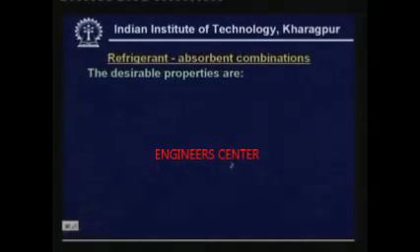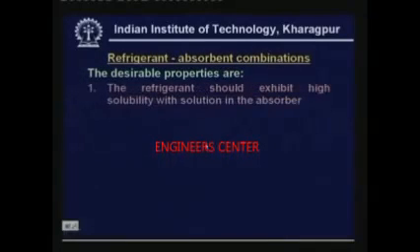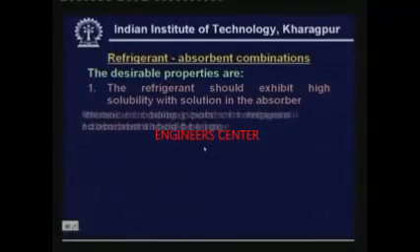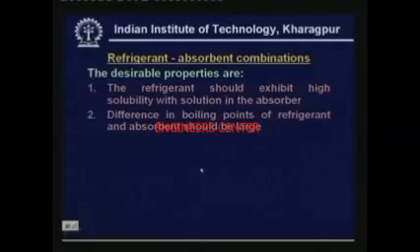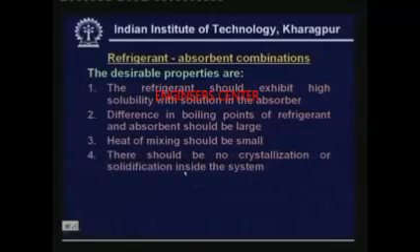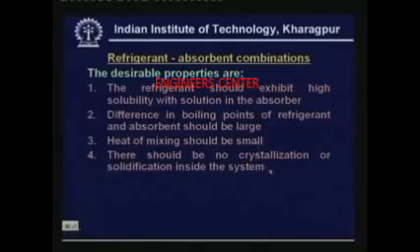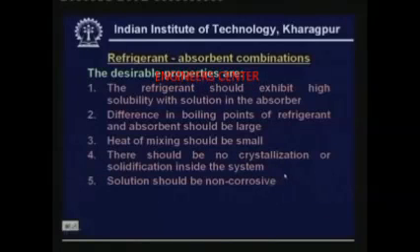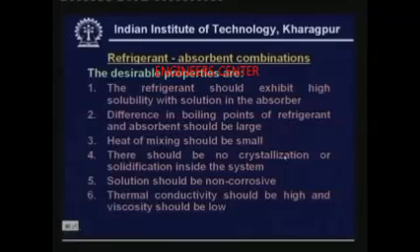The desirable properties for refrigerant-absorbent combinations are: the refrigerant should exhibit high solubility in the absorber; the difference in boiling points should be large so that only the refrigerant boils in the generator; heat of mixing should be small — though points 1 and 3 are contradictory; there should be no crystallization or solidification inside the system; the solution should be non-corrosive; and it should exhibit good transport properties, meaning high thermal conductivity and low viscosity.